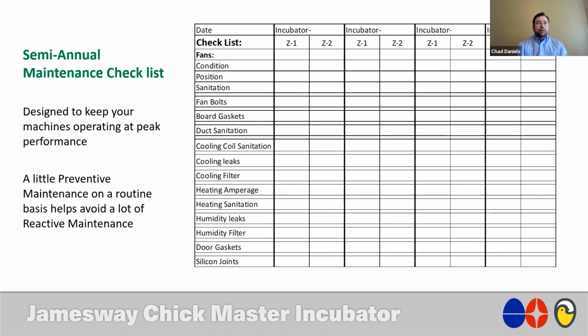And then of course, I've got heating amperage, and I put that on there because I think it's important, regardless of the age of your machines, to semi-annually force the heating to function and then take an amperage reading of those heating elements. And that way you have that documented. And so when you look at that from a zonal standpoint, on a ducted machine, you only have 2 heating elements. You've got one for zone 1 and one for zone 2. On a Millennium machine, you've got 6 heating elements, but the 3 in the front function together, and they're all tied to the same service. So it's important to semi-annually check the amperage on that.